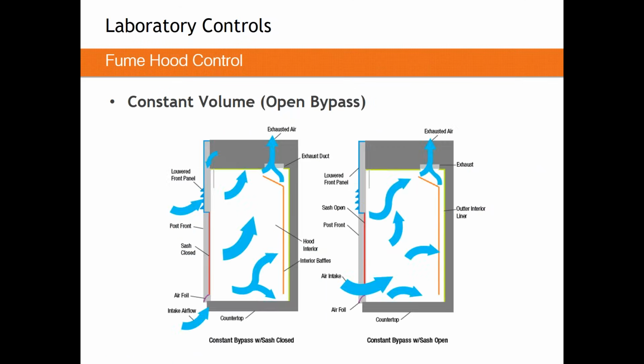Essentially what's going to happen is there's going to be an open bypass. So on this hood, you can see the louver system on the front of it. On some fume hoods, that open bypass will be in the top of the fume hood or the sides of the hood. They come in a few different shapes and sizes. But as the sash opens, we're going to proportionally close that open bypass, and we're always going to exhaust a set constant volume amount of air. This is a good application for a mechanically set constant volume Venturi valve, just by the way.